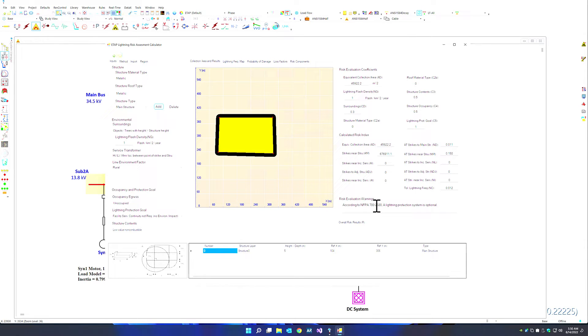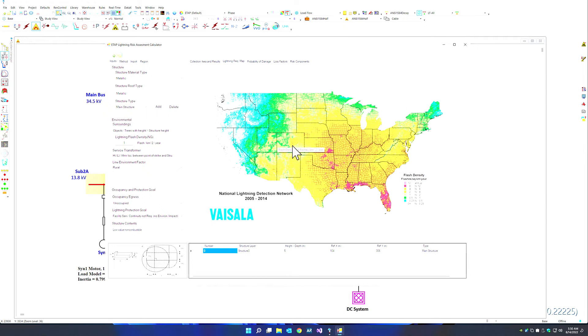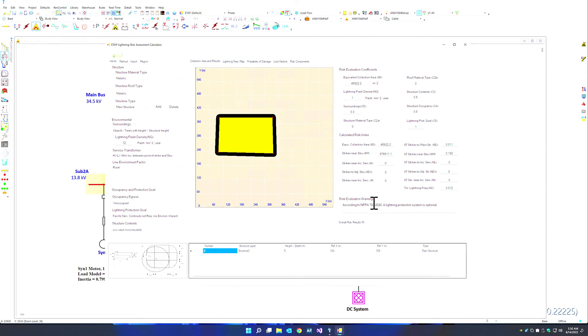According to NFPA 780, a lightning protection system is optional in this particular case, with a lightning flash density of one flash per kilometer square per year. We can go to our lightning frequency map and pick from a different lightning density, such as 12 flashes, which is updated within our calculator. Going back to our simulation, you can see the protection system is still optional.